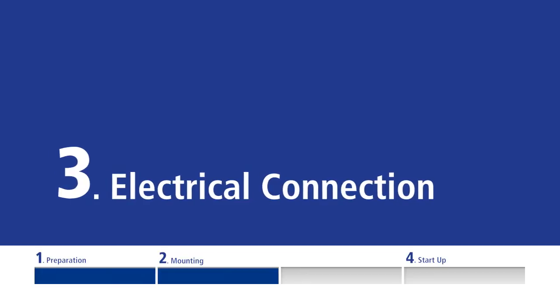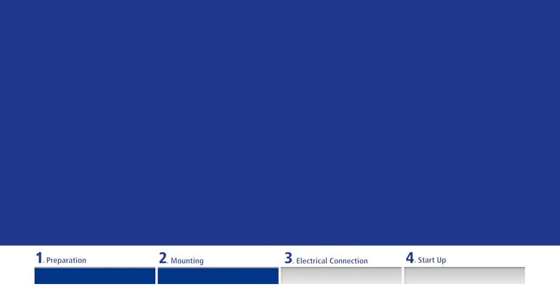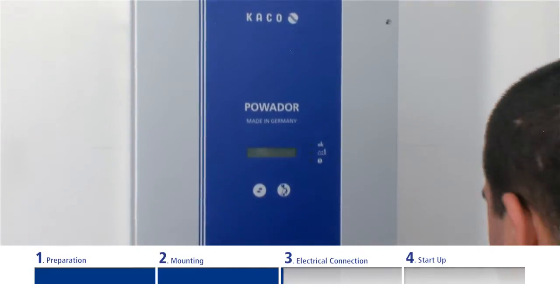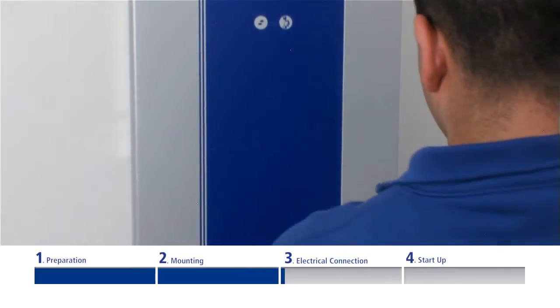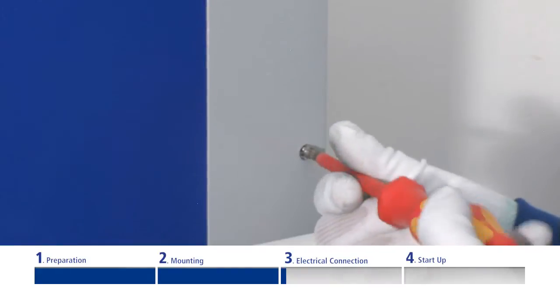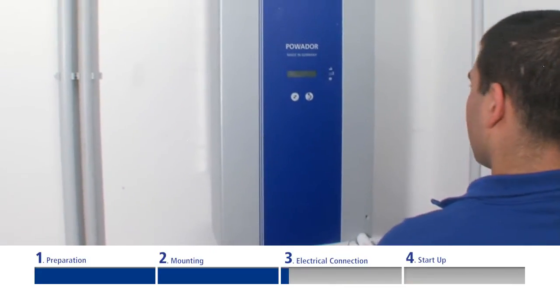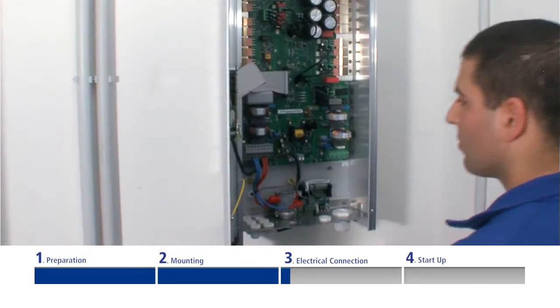The electrical connection. The inverter connection is established via PCB terminals in the inverter's connection area. The door of the housing must be opened to do this. Temporarily remove the two Phillips recessed head screws on the right side of the door housing.